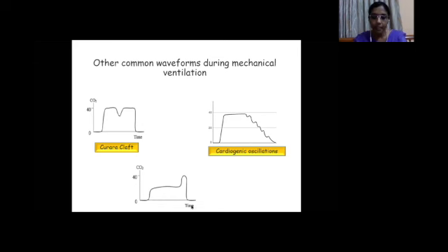And in this case, yes, the baseline is okay, but the waveform has not reached the normal height. At the end of the plateau phase, we suddenly see a spike and then there's a downstroke. This is commonly seen when there is a leak in the sampling line. The EtCO2 value that we read may be normal because it is measured at the end of the plateau phase. Why does this happen?